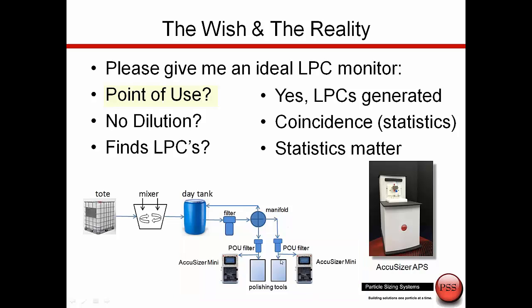And part of that is because large particle counts actually are created in the process. And since they're created in the process and affected by the process, we want to take the measurements in the process. And lots of customers said, hey, what I'd like to have is a system where I don't have to do any dilution. I don't want to deal with any of this messy stuff of dilution.